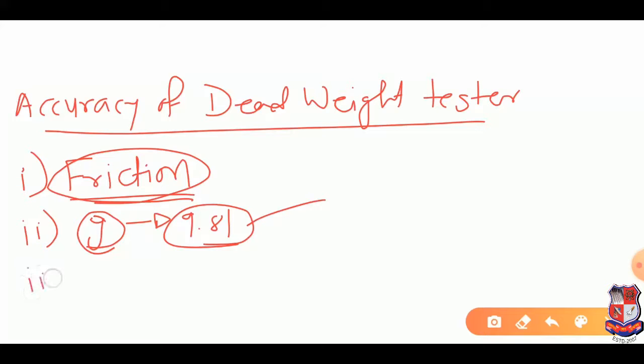The third parameter is uncertain value of effective area. The area upon which the weight force acts is neither the area of piston nor the area of cylinder, and it is somewhere in between these two values. The effective area depends upon the clearance, spacing and viscosity of oil. There are some other factors such as uncertainty in mass of loading weight, air buoyancy on weight or fluid buoyancy of piston, then thermal expansion and elastic deformation of piston and cylinder. So this is about the dead weight tester.